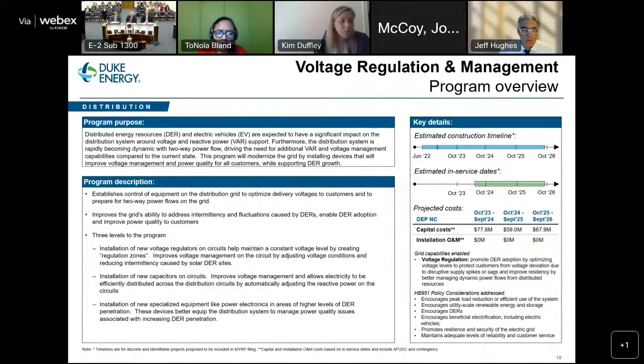The first is additional voltage regulators installed on the grid to manage those fluctuations. For existing voltage regulators, we install new controls capable of determining two-way power flow. Current controls look at the substation as the stiff source of power and only regulate voltage downstream of that; these new controls have to look in both directions.